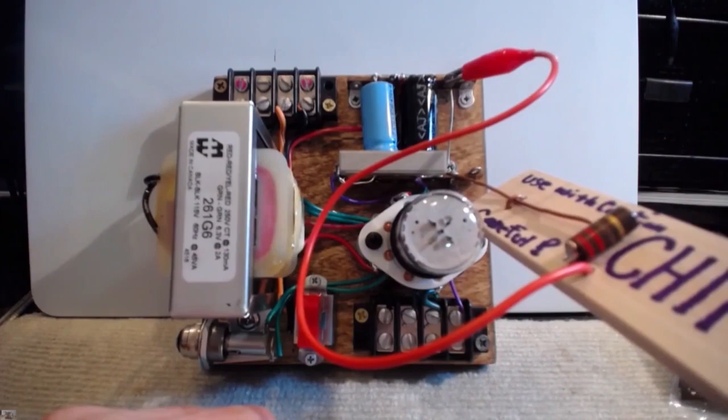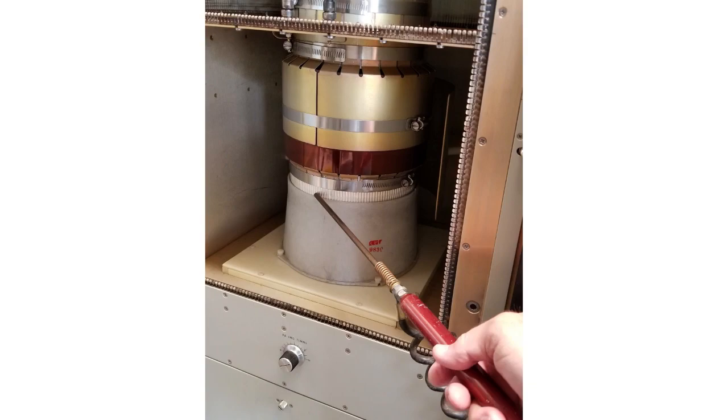Let's look at this next photo here. This is often referred to as a Jesus stick or a lot of other names. The photo is really a little out of scale because of the angle I shot it. But that's the whole rig there, probably just under two feet long. And you can see there's a coily coil coming out the bottom. That's not a microphone cable. That's a heavy gauge stranded conductor inside of there that ties to ground.